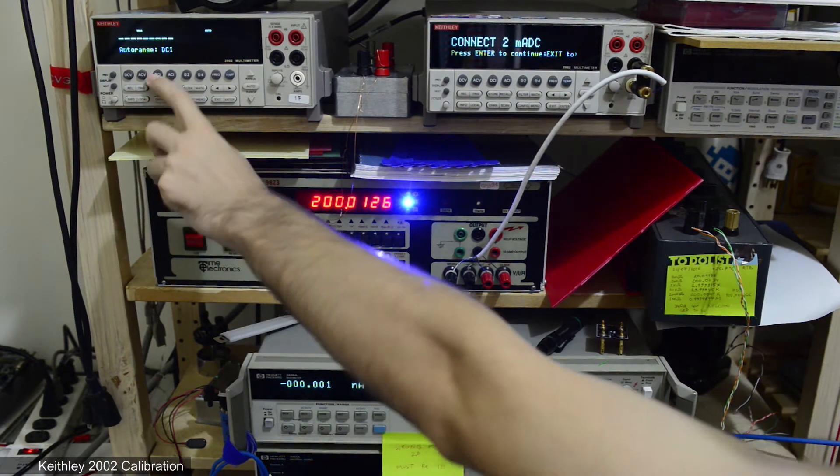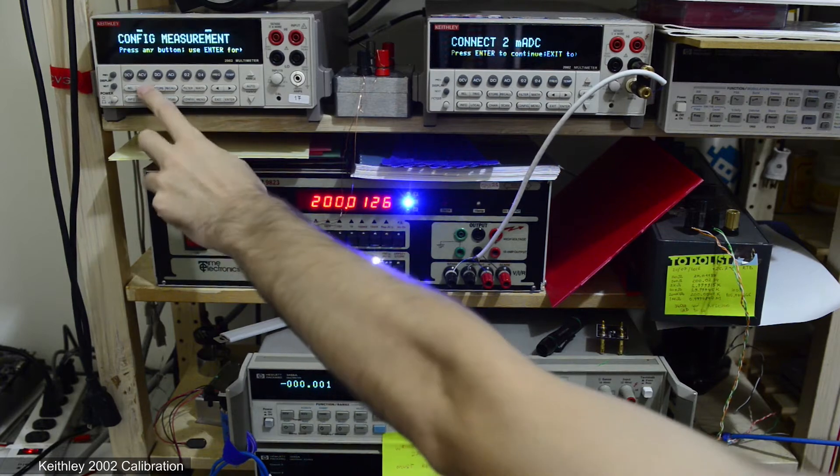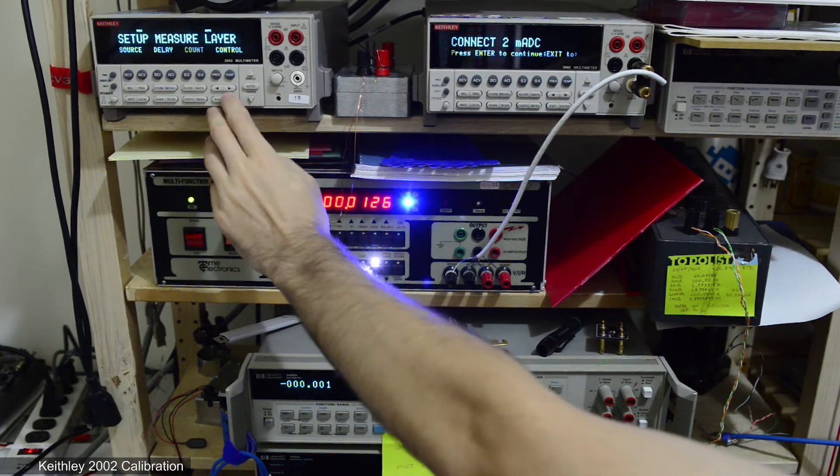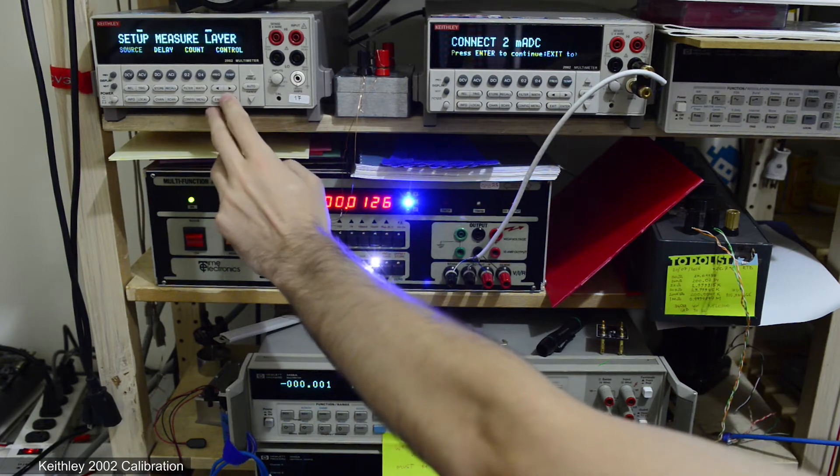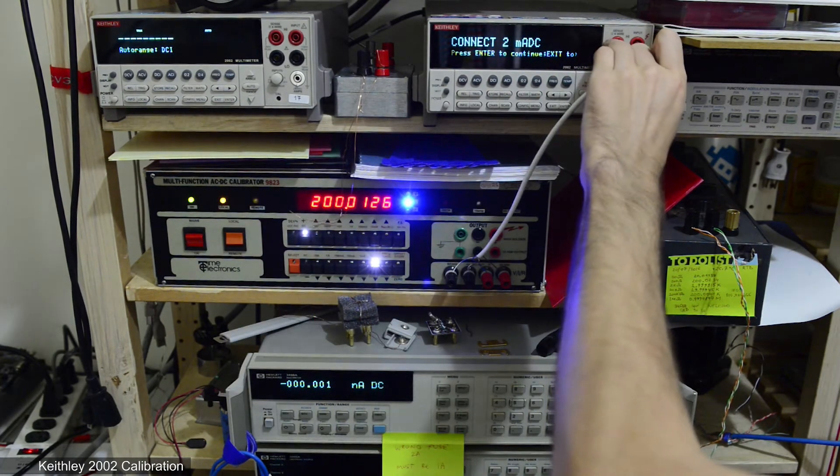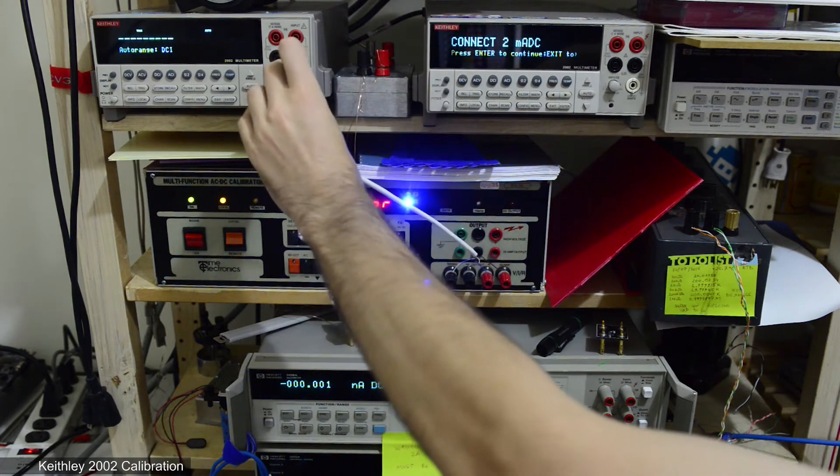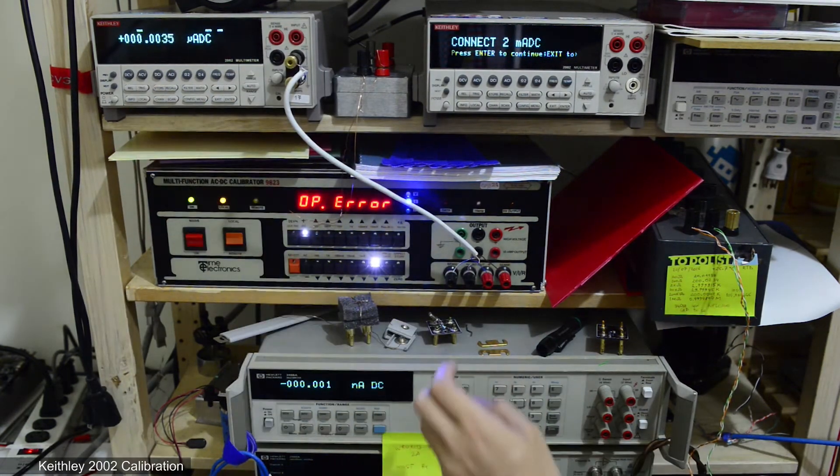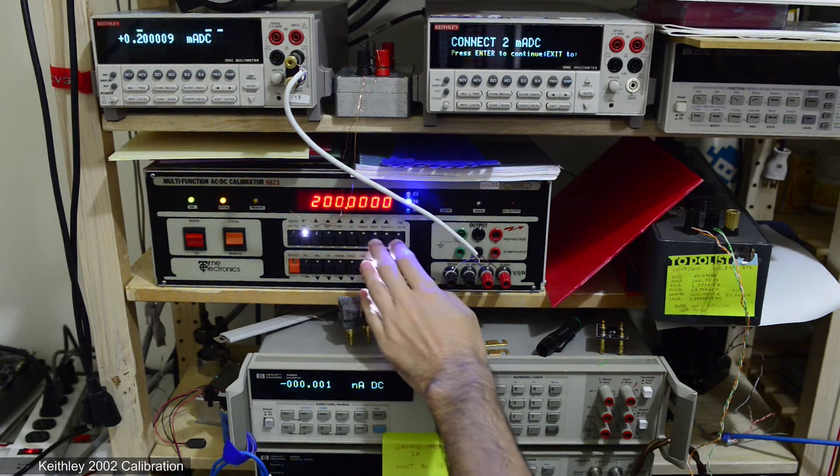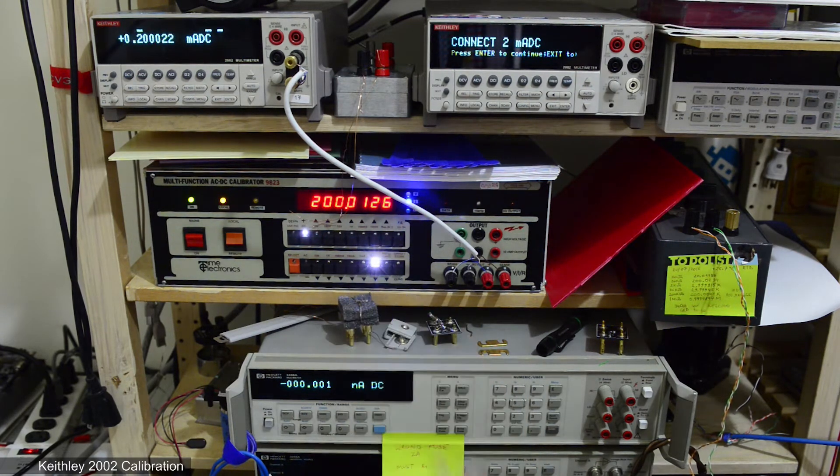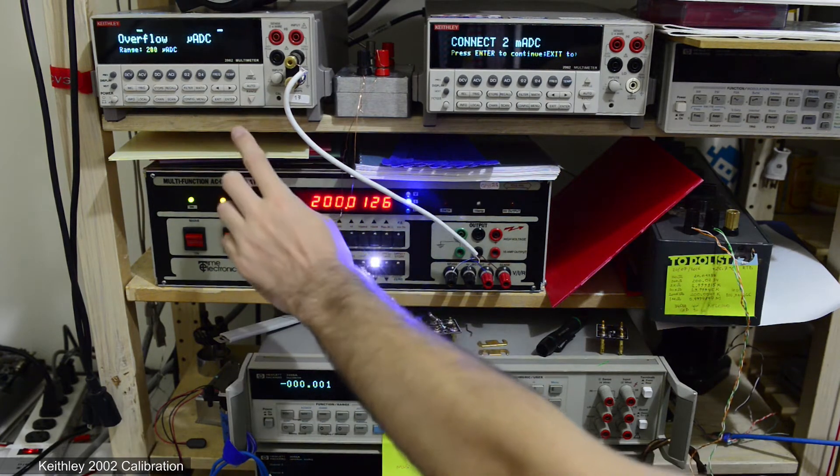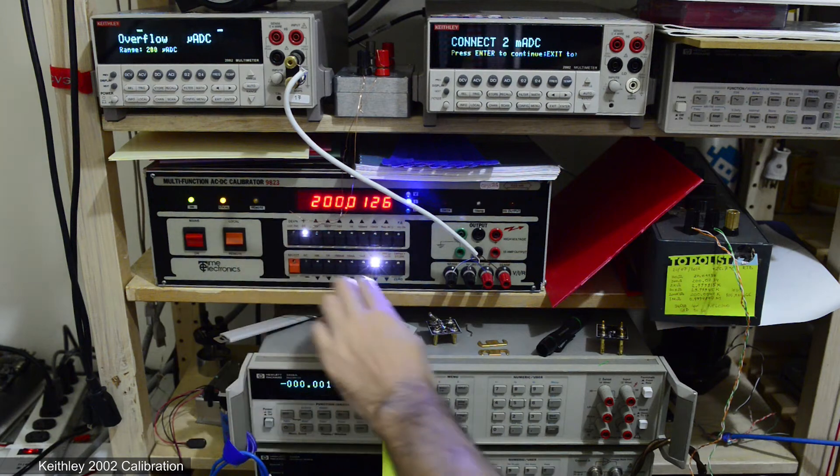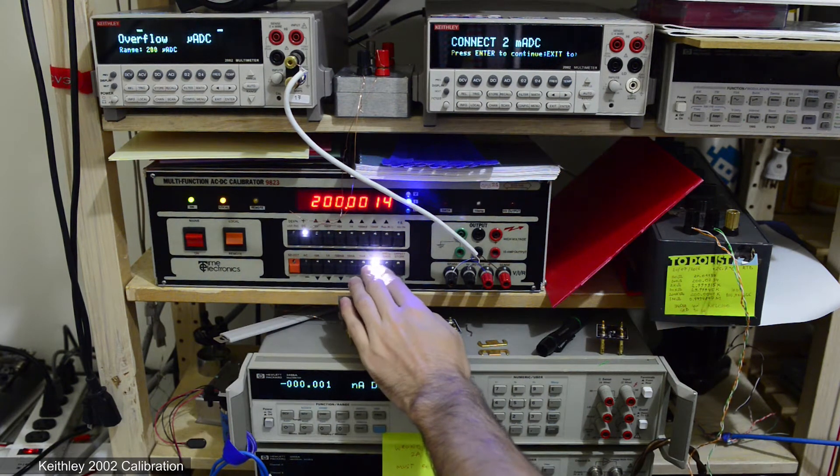So to check what's the problem I connected current output to another Keithley 2002. And we'll see what it shows. As you can see on 2 milliamp range the DMM shows just fine. But on lower range 200 microamp it just shows overflow. While it should be 200 microamps.